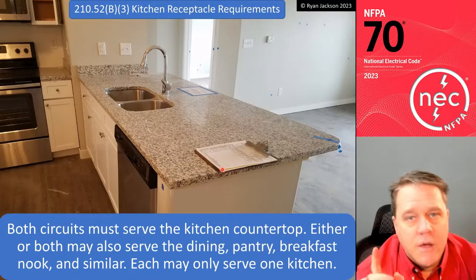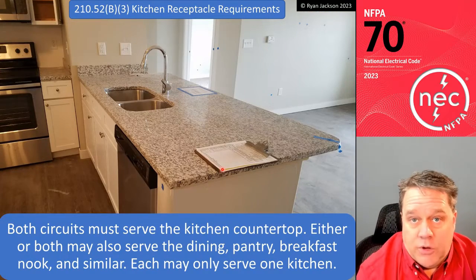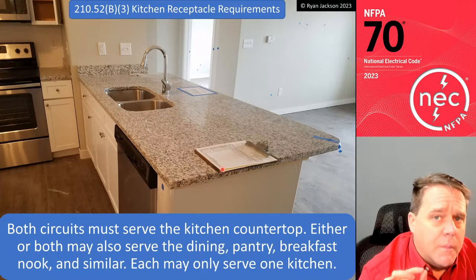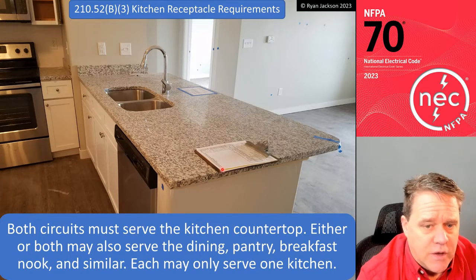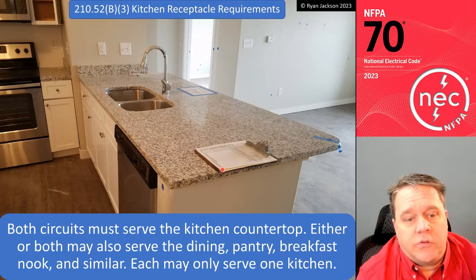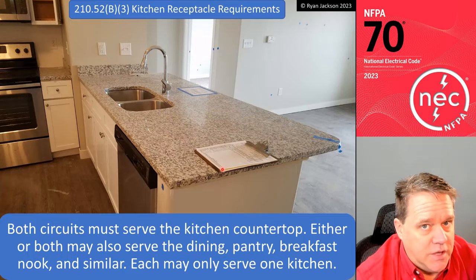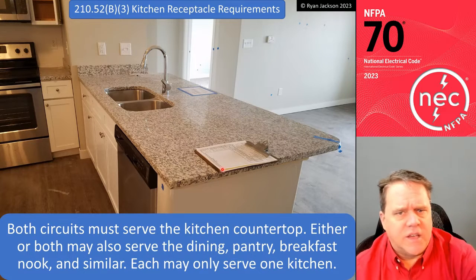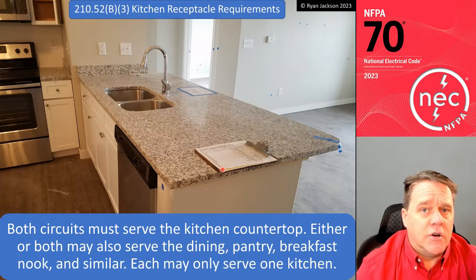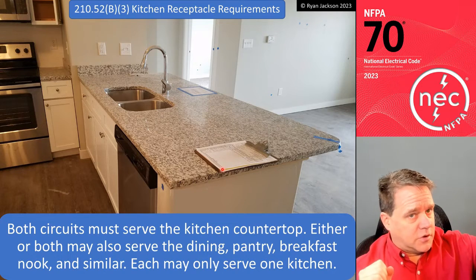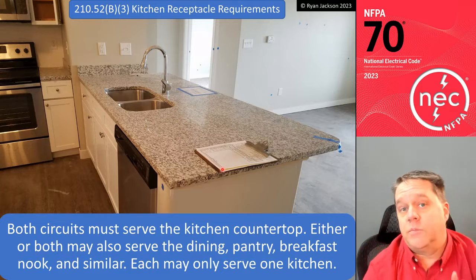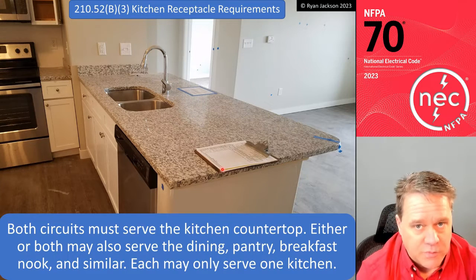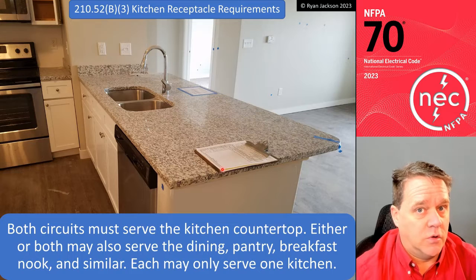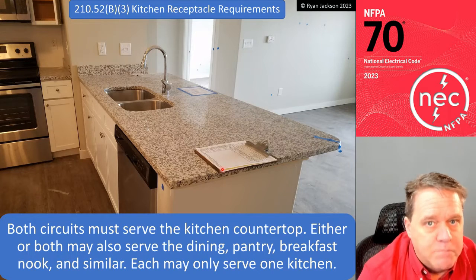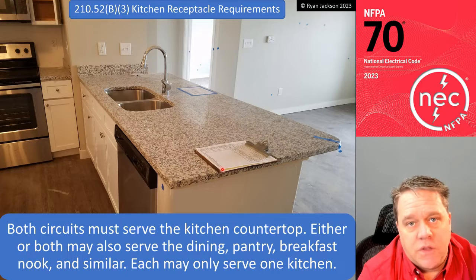Let's keep reading. 210.52 B3, the last thing in B, says both circuits must serve the kitchen countertop. Either or both can also serve the dining, pantry, breakfast nook, and similar, and each may only serve one kitchen. All right, so let's knock out the second sentence first. If you have 2 kitchens in your house, you need to have 2 small appliance branch circuits for one, 2 different small appliance branch circuits for the other one. So 2 small appliance branch circuits per kitchen, and they can only serve one kitchen. Both of the circuits have to hit the kitchen countertop.